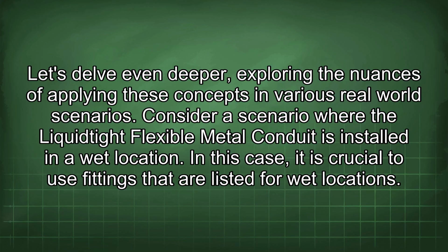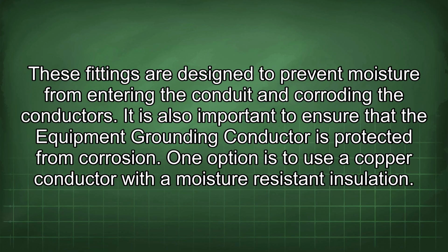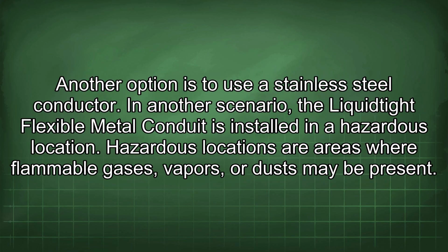Consider a scenario where the Liquatite flexible metal conduit is installed in a wet location. In this case, it is crucial to use fittings that are listed for wet locations. These fittings are designed to prevent moisture from entering the conduit and corroding the conductors. It is also important to ensure that the equipment grounding conductor is protected from corrosion. One option is to use a copper conductor with a moisture-resistant insulation. Another option is to use a stainless steel conductor.